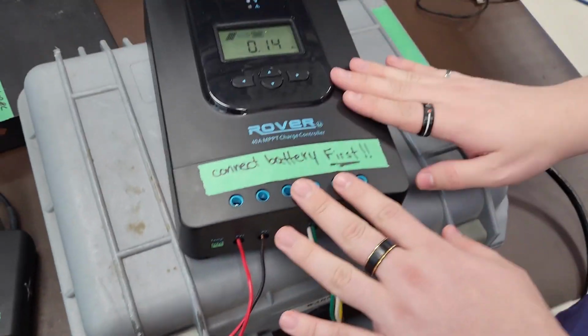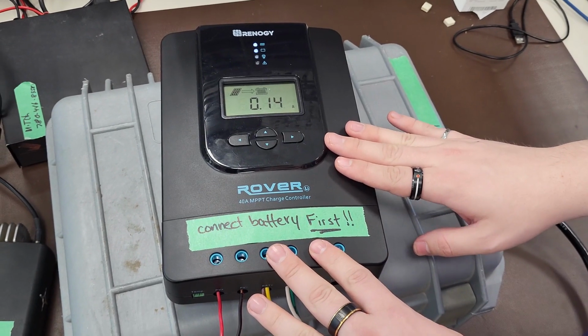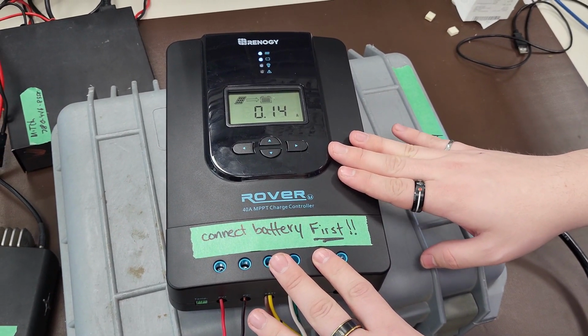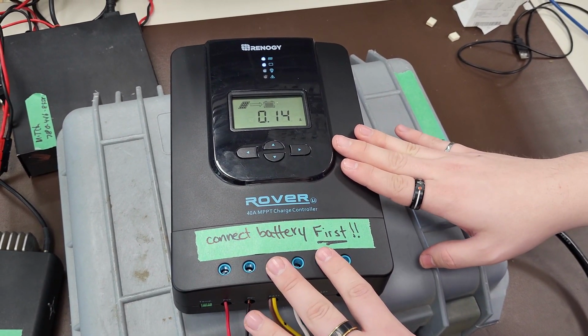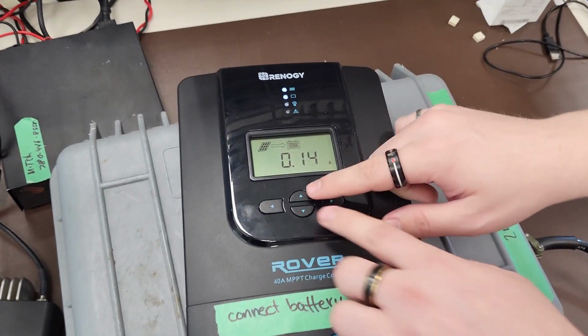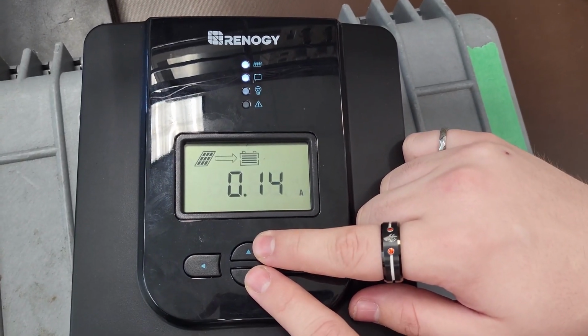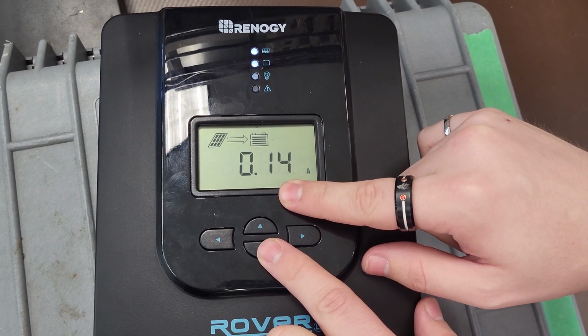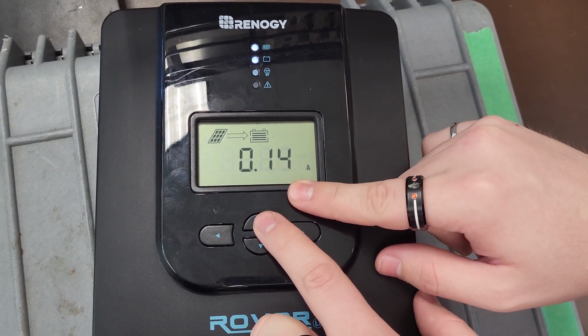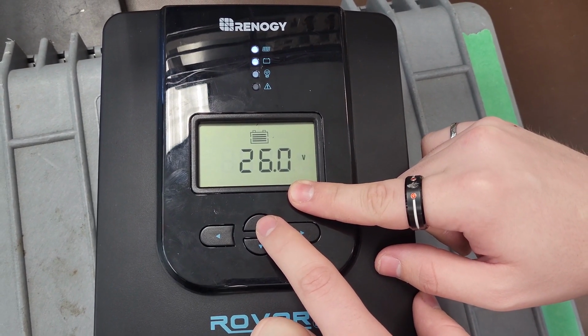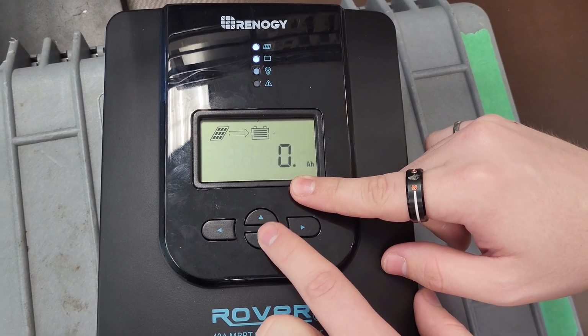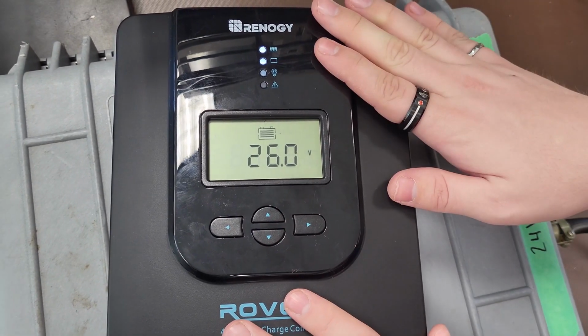This is here to prevent overcharging of the batteries and prevent voltage spikes from the solar panels from frying the batteries. You'll see here it has multiple different settings. We can check the amperage going from panels to batteries, the panel voltage, the battery state of charge, and the battery voltage, alongside some other functions if we attached a load to this charge controller, which is not part of our system.